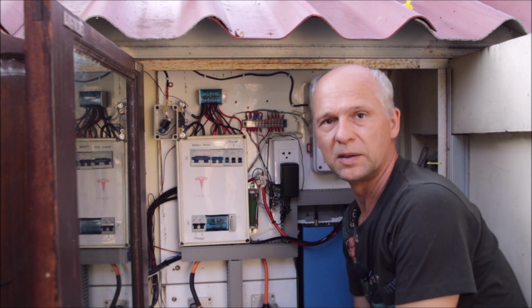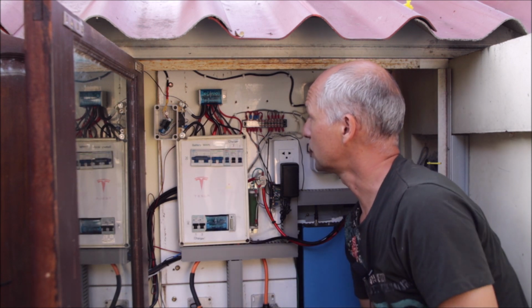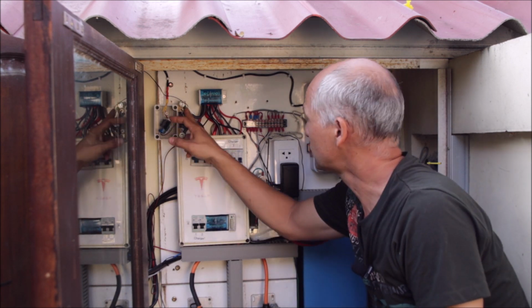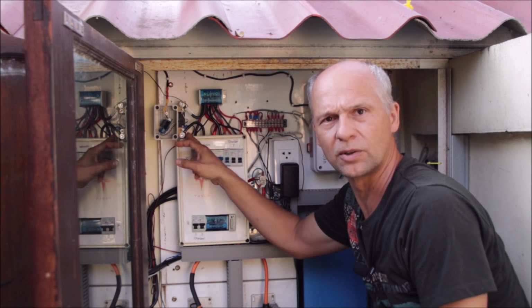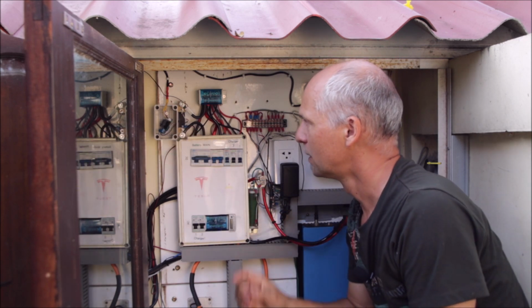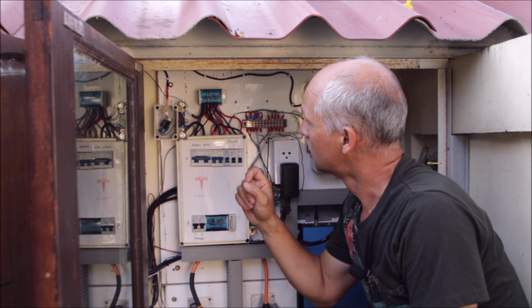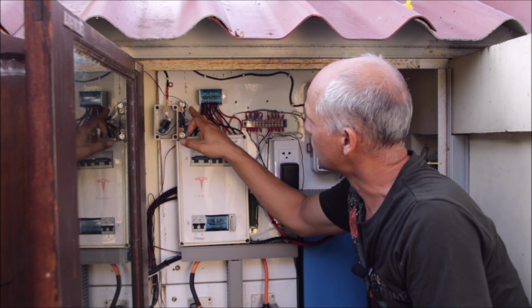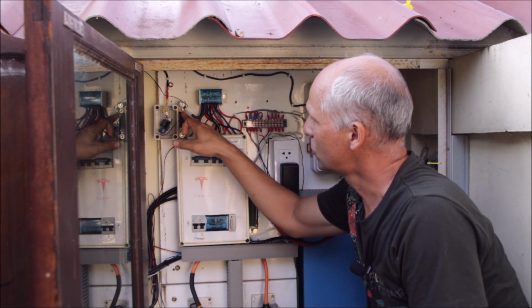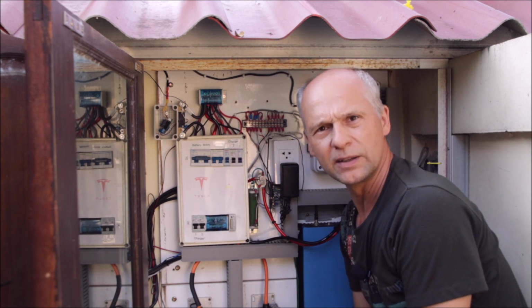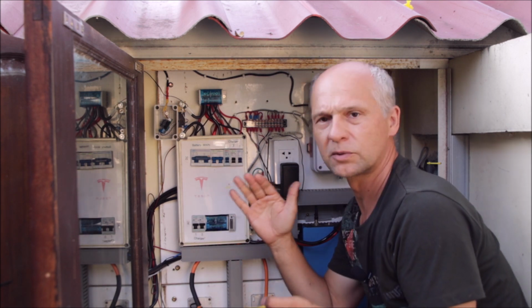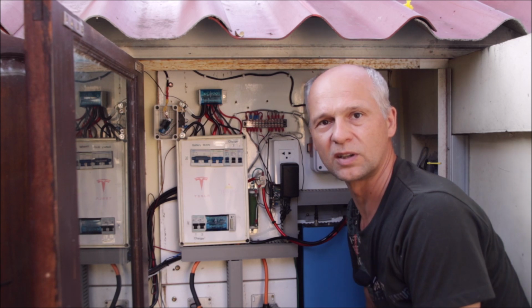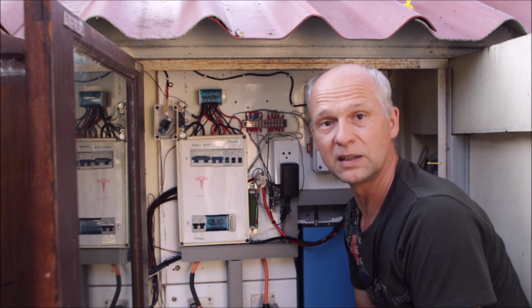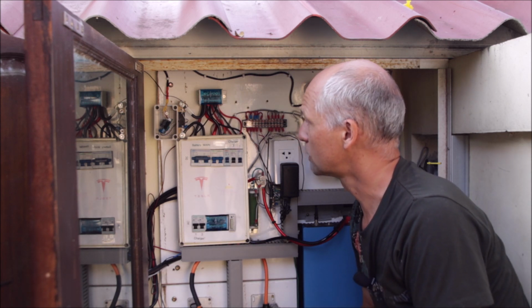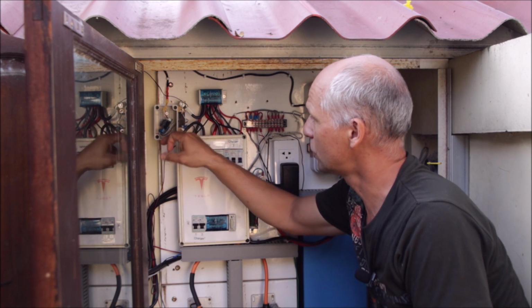So as you may already know, our coulomb meter works the way that we have a shunt. The shunt is producing, depending on the current flowing over it, a certain voltage drop. These shunts typically are rated so that at maximum current they produce around 75 millivolts of voltage, and that voltage is then measured.